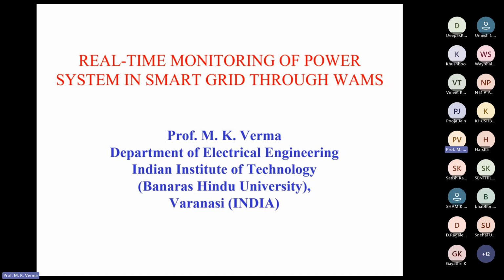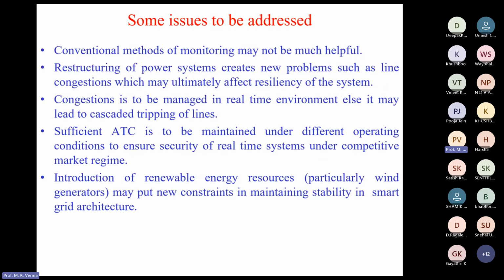Now I will talk about real-time monitoring of the system in the smart grid through a wide area monitoring system. What issues are to be addressed in the wide area monitoring system? The conventional methods of monitoring are not much helpful. Earlier, when something happened, there were phone calls from the operators to somebody in the control center, and that was not clear. The clearing of faults took time because there was sometimes miscommunication. Now, in the smart grid architecture, we can monitor the health of the system through SCADA and the wide area monitoring system.